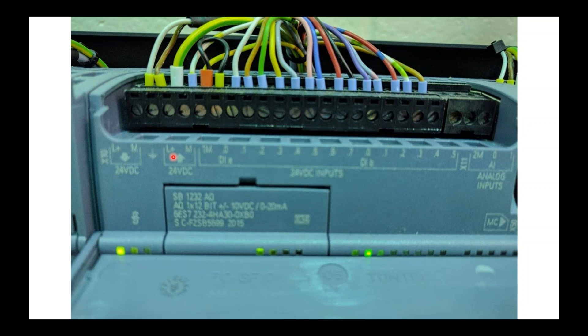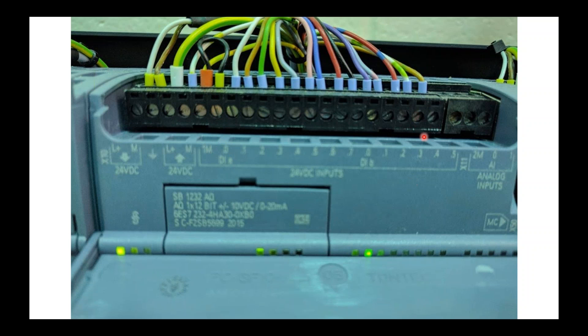This is your positive out and M in, your common out. Here where it says 1M, that's looking for another common. And you can see that it's just jumpering from one side to the other. How we power these inputs is we take L+, for instance, to feed that out to my output and feed that out to my switches and then as they kind of link it together and daisy chain together. And on the other side of the switch, each individual switch, we will run to each one of these terminals to represent an input.